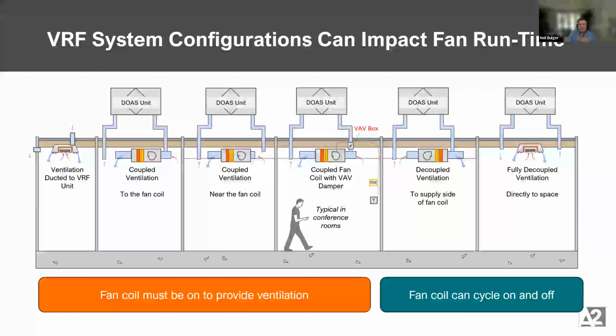Even in VAV reheat systems, it's usually best to let the model size the reheat coil. There are so many nuances that might be different about how you zoned your model compared to how many attributes are in the actual VAV box. So I think that's kind of true for VRF too. When you get down to zone capacities, maybe care a little bit less about being specific and focus more on ratios. Is it the right fan power to airflow? Is it the right turn down ratio? Is it the right sensible heat ratio? Things like that, the fan coil.